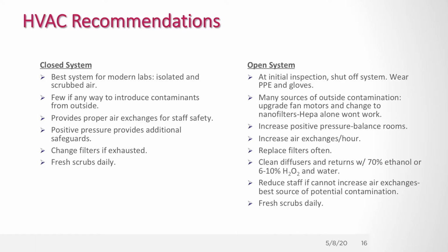If possible, do that. If you can't, try to increase your positive pressure, which often means balancing the air in the laboratory. Increase your air exchanges per hour so you remove aerosol as quickly as possible. Replace these filters as often as you can, and make sure you clean the diffusers with something like 70% ethanol or 6 to 10% hydrogen peroxide.